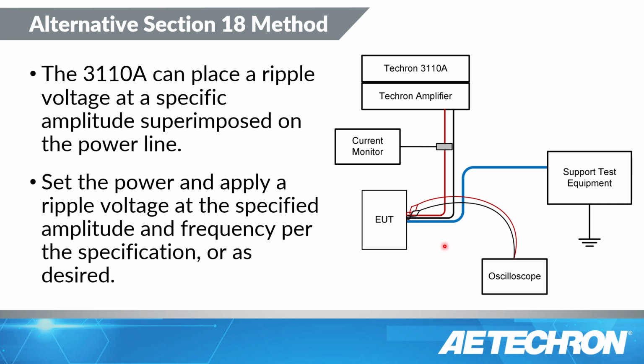When doing this test, I always recommend, first off, do the voltage measurements as close to the EUT as possible, especially if your equipment takes a lot of current, because that wire will experience a voltage drop. And we need to assure that you're testing at full level. You also need to monitor how much current is being injected into the system. So you do need a current monitor of some type.